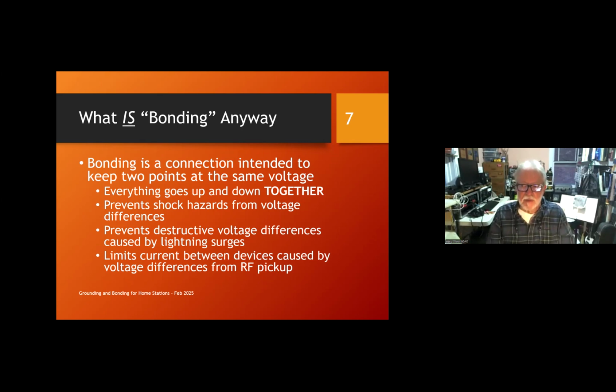When you have a lightning surge, when Mr. Lightning comes to call and you have a big current through your station for whatever reason, whether it's in the antenna part or the transmitter or whatever, when you have everything bonded together, it goes up and down together. Then you don't get this terrible destructive voltage surge where one part of the station goes way up and the other part of the station is still down here. So you get a lot of current flow. That's what drives the destructive current flow, is the voltage difference. So if you can get all of the equipment to go up and down together, you can minimize the destructive voltage differences. That's what bonding does for you.